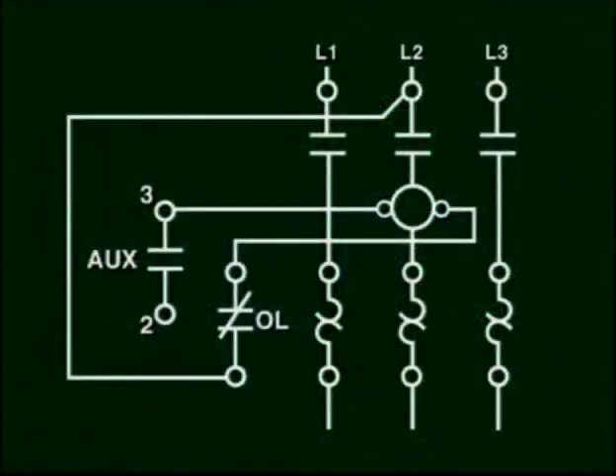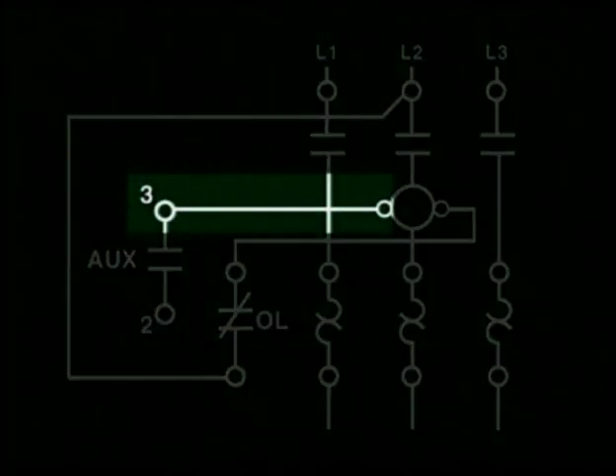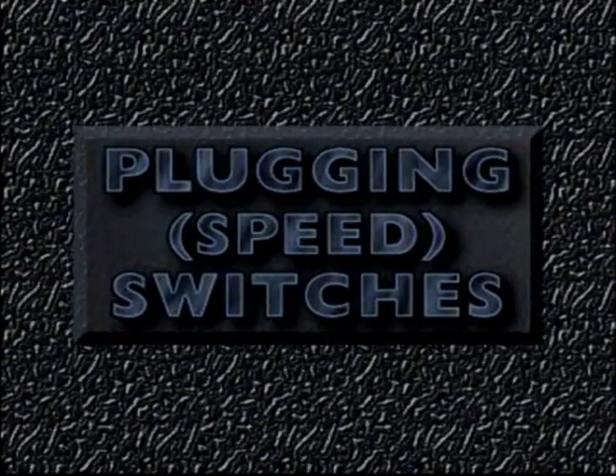Most motor starters are supplied from manufacturers with some pre-wiring. These include the wire that goes from one side of the starter coil to the normally closed overload contacts, and then from the other side of the overload contact to the return or L2 terminal connection on top of the starter. The other pre-wired connection is from one side of the auxiliary contacts labeled Terminal 3 to the coil. This side of the coil is where control power is connected to turn the starter coil on. As will be seen, these connections save a lot of time during installation of three-wire motor control circuits. Let's now look at plugging switches and their operation. Plugging switches are used to stop or brake a motor rotation in a quick and fast manner.